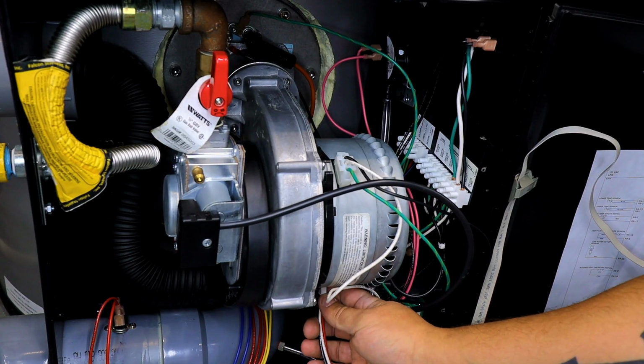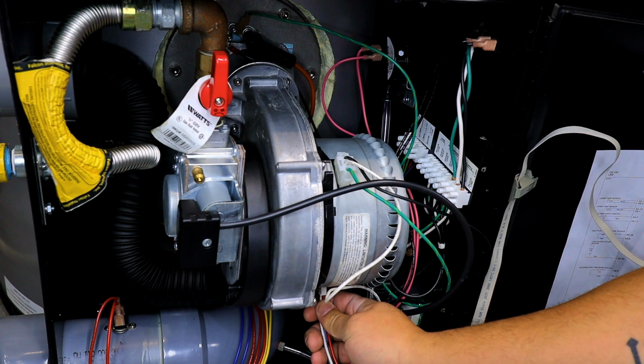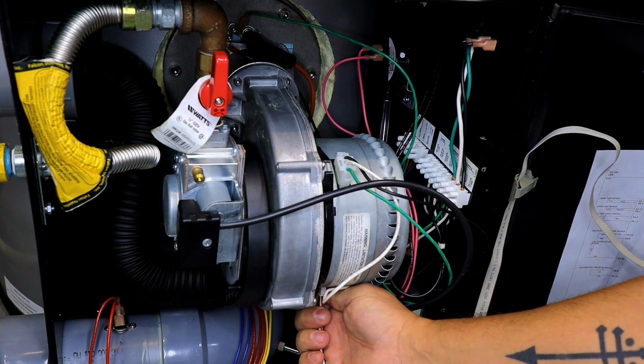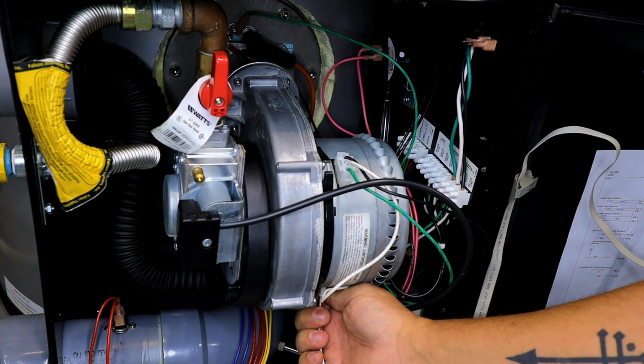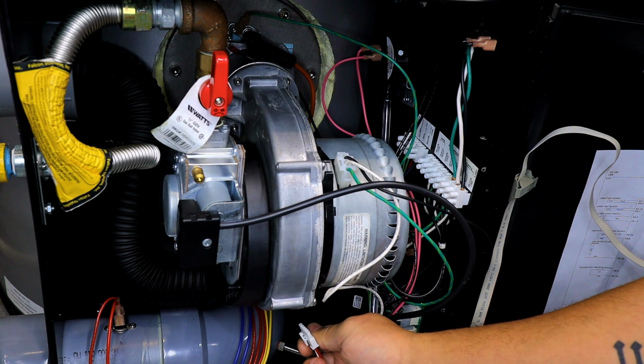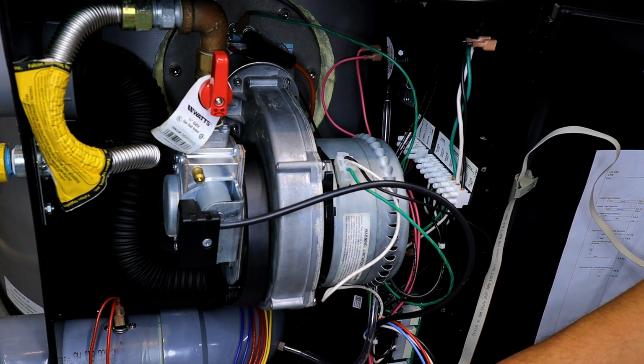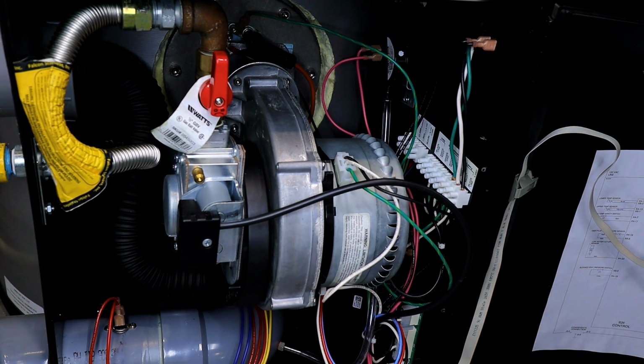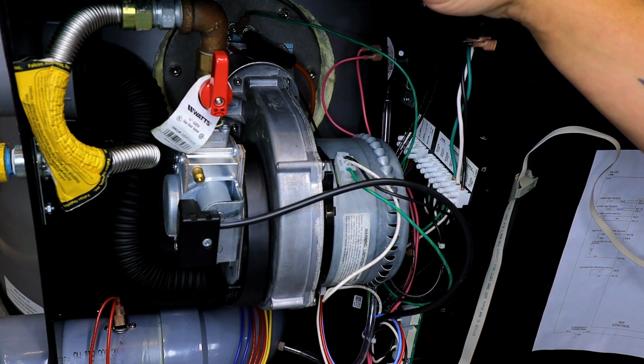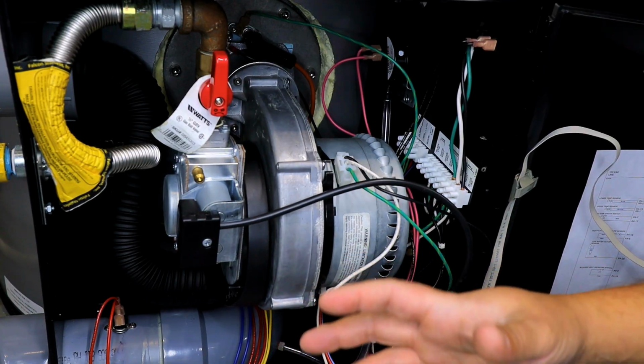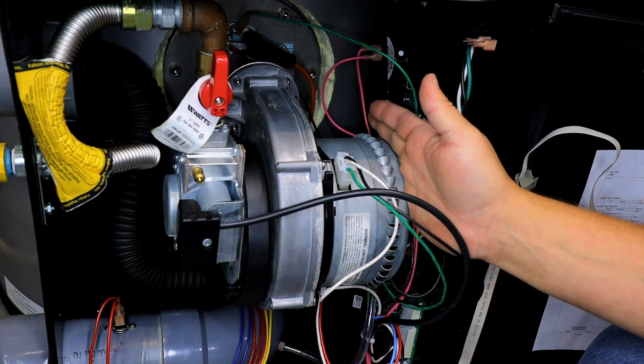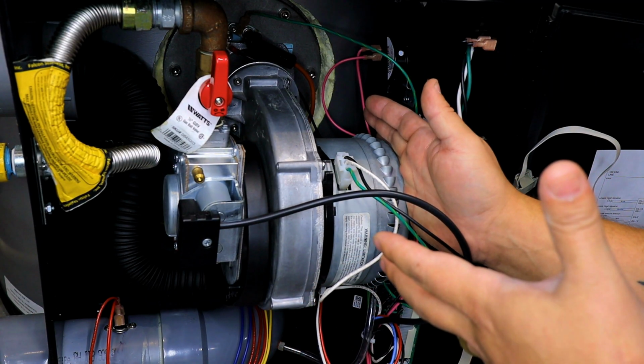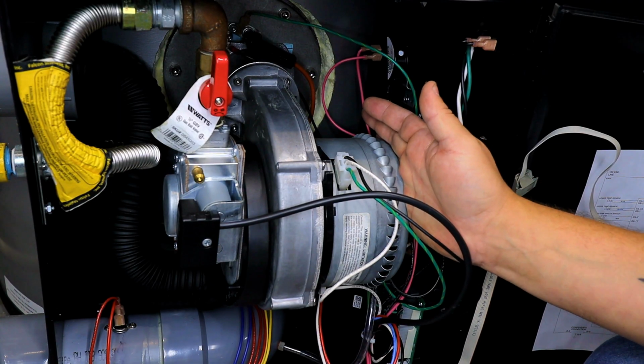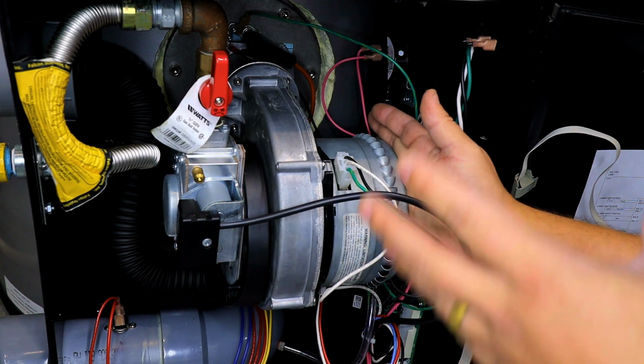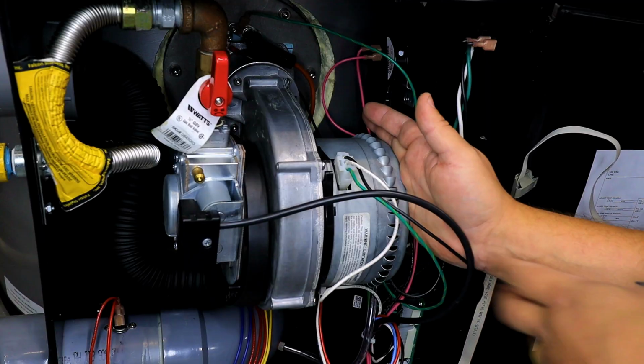The second thing we can do is actually unplug while energized this low voltage input, and what we should see is the fan should take off running. Just like that. Now what this confirms is that the fan is actually functioning with just 120 volt input and no control voltage. That means our fan is not seized, and one way to confirm that our fan should be in good shape.